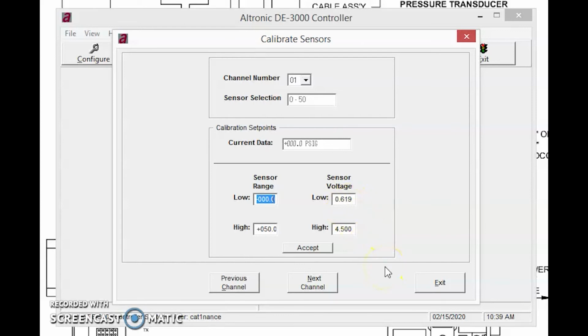Again, if you're having to do this constantly, more than likely we either have a loose wiring connection or a faulty, damaged pressure transducer, and we should change that. But from time to time, it's very important, especially on DOT type locations, to calibrate pressure transducers. And this is a perfectly acceptable method. There's another way to do a low tweak calibration method, through the DE-3000 terminal or display unit through the keypad, but I don't really recommend that. This is the preferred method, and it's worked out really good for me over the years.